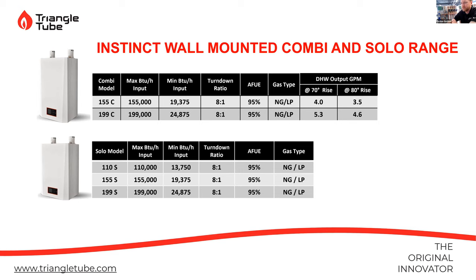Looks like we got a couple more questions coming right now. Yeah, there was one question that happened here. If it's a mod boiler, why do you need to derate the boiler? I'm just typing in an answer here to that one now. Yeah, it'll just prevent it from going into high fire. So for instance, my boiler at home, I got a 199. My load in my house is about 60,000 BTUs. I derated it to 50%. My boiler has never come out of mid fire. It's always stayed in the low to mid fire region.